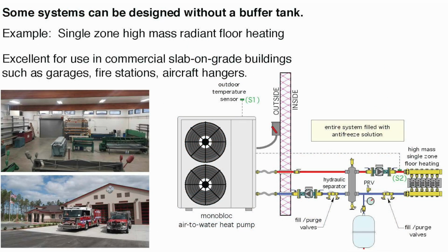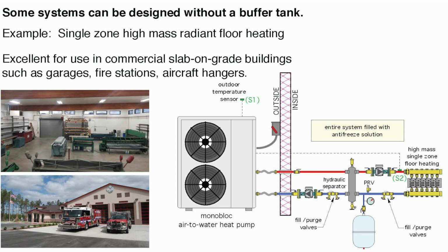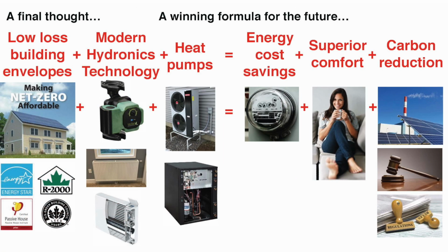Here's kind of a unique application. This is where you've got a slab-on-grade building. Think about a Midas muffler shop. Do you have Midas muffler up here? Vancouver? Okay. Midas, any kind of a commercial slab-on-grade, new construction, radiant floor heating. You don't need a buffer tank. You've got huge thermal mass in that concrete slab. So you can just connect a hydraulic separator between the heat pump and the radiant floor, keep the system really simple, use constant circulation in the floor, and just run the heat pump as a heat injector into your distribution system.